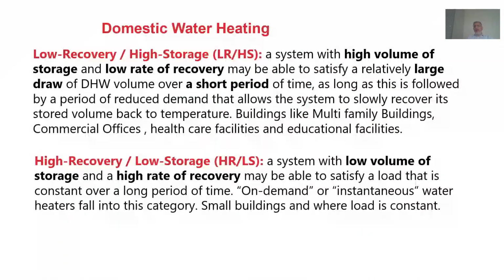On the domestic water side, there are basically two types of domestic water system. One is low recovery and high storage, and the second one is high recovery and low storage. A quick difference between the two: the low recovery machines store a high volume of water and have a low rate of recovery, meaning the power or the hot water produced by the machine is low compared to the high recovery machine.